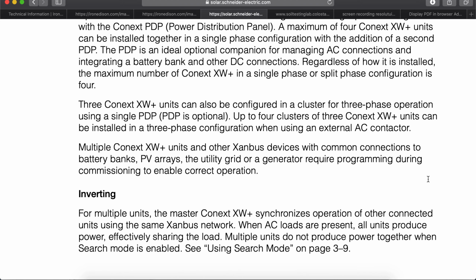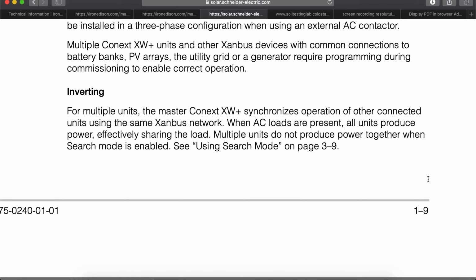Multiple Conext XW Plus units and other Xanbus devices with common connections to battery banks, PV arrays, and the utility grid or a generator require programming during commissioning to enable correct operation. For multiple units, the master Conext XW Plus synchronizes operation of all other connected units using the same Xanbus network. When AC loads are present, all units produce power, effectively sharing the load. Multiple units do not produce power together when search mode is enabled. See using search mode on page 3-9.